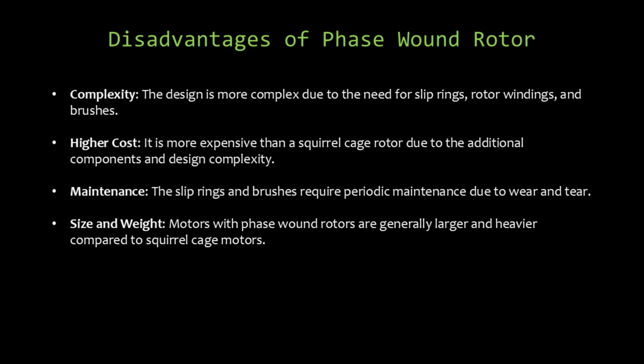Despite their advantages, phase wound rotors come with notable drawbacks. The design is more complex, involving slip rings, rotor windings, and brushes. This complexity translates to higher costs and increased maintenance requirements. The slip rings and brushes experience wear and tear, necessitating periodic maintenance. Additionally, these motors are generally larger and heavier compared to their squirrel cage counterparts.